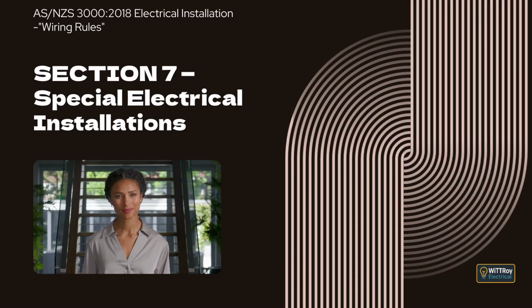It explains that suitable switches or devices must be provided for starting and stopping the generation system, and where more than one control device is used they must be grouped together and clearly identified. It also explains that the system must be arranged so it cannot supply energy upstream of the point of connection to the installation, either directly or indirectly, unless a formal agreement exists with the electricity distributor. The clause notes that conditions for grid-connected and cogeneration systems operating in parallel with the network are outside the scope of this standard.